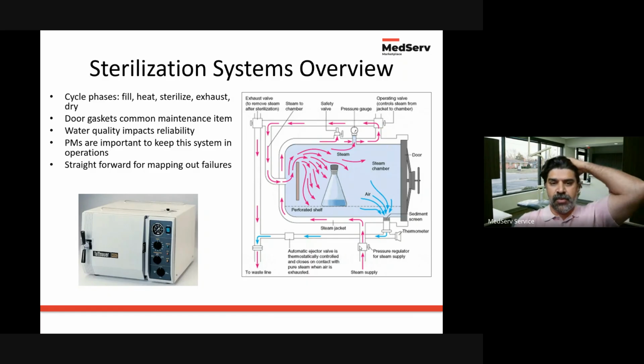Looking a little bit closer at probably one of the most important pieces of equipment in the sterilization center, the autoclave. This uses a combination of heat, pressure, and steam to eliminate microorganisms from dental instruments between patients. Most of the failures typically occur when it's filling up with the steam, air, and heat combination, or when it's trying to empty out and dry, the removal of moisture. These issues typically happen from worn gaskets, clogged drains, or the heating element not working properly. Some of the sensors can also throw off errors.